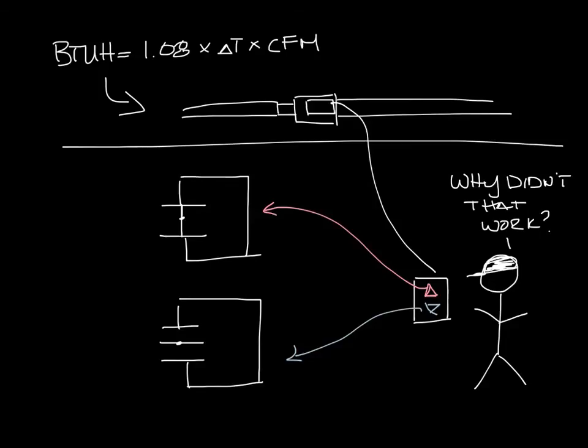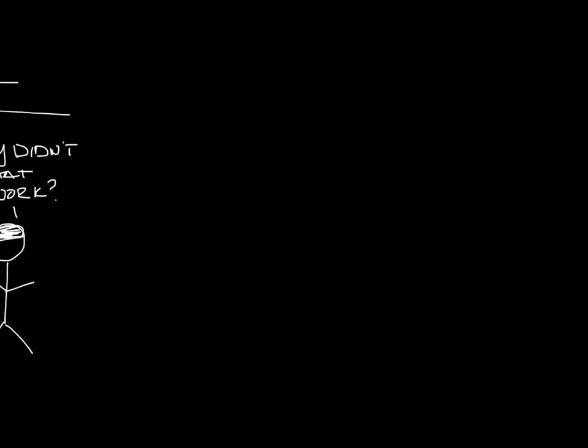So let's move this over and look at what happened. What he might be forgetting here is that most VAV boxes are pressure independent and the VAV box controller is set to control from a minimum CFM to a maximum CFM, not from damper open to close.